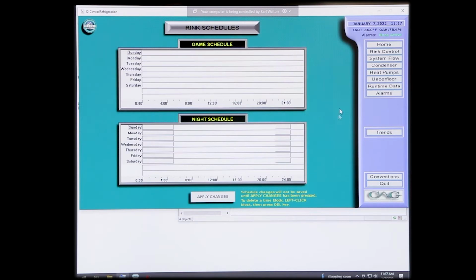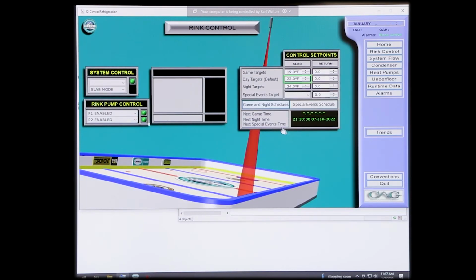All right. So now back to Rink Control. So now what it's going to tell you is your next night time is 21:30 today on the 7th. So it's going to run that way through. So you're going to run at a 24 at that time, 24 slab. Okay? And at 5 o'clock in the morning, it's going to restart and look at the new target of 22 and run the machines.